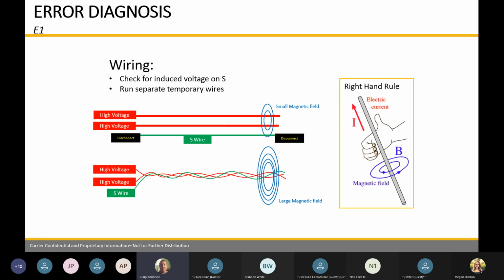So just your wiring, like I said, it's a signal wire. So L2 and S are your signals, and then L1 and L2 is your power. So you've got to be mindful that L2 is a signal wire as well. If you have an electrician going out there to wire, they don't differentiate L1 and L2. So be mindful before you flick a switch that he has them correctly, or we're going into an E1 code.